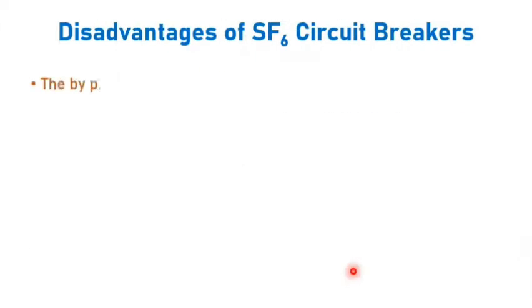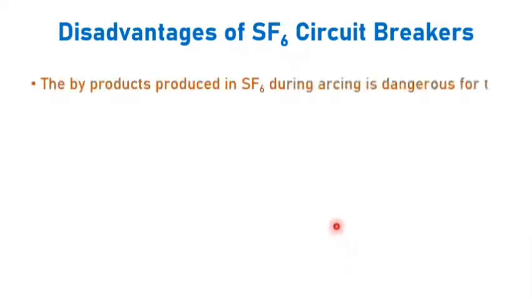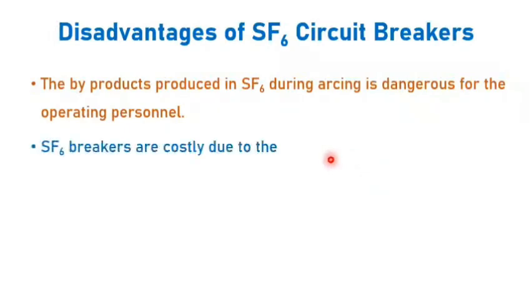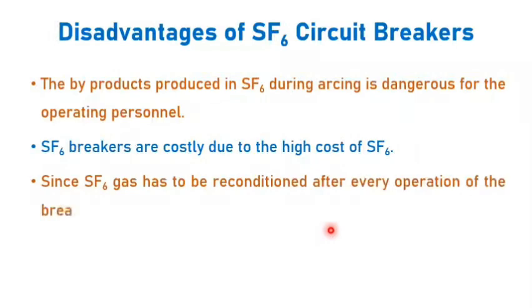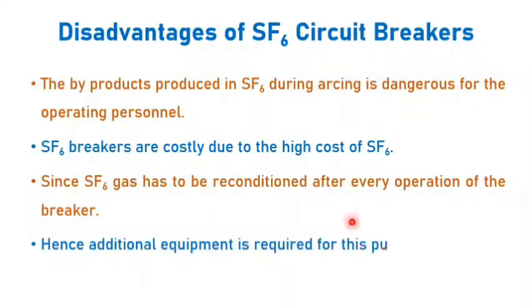The main disadvantage is that the byproducts produced when the SF6 gas is released may be dangerous to the operating personnel. And since SF6 gas is costly, the circuit breaker itself becomes costly, and SF6 gas has to be reconditioned after every operation of the breaker. Hence additional equipment is required for the purpose of reconditioning.